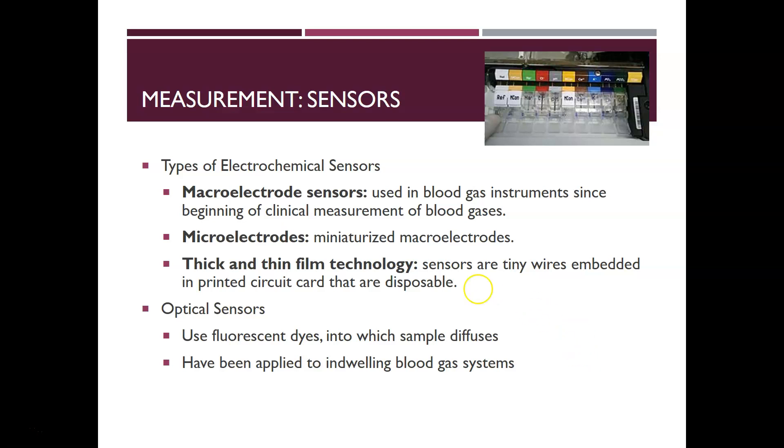Different sensor types are available. Macro electrochemical sensors have been used in blood gas instruments since the beginning of clinical measurement. As technology modernized, instruments were miniaturized to micro electrodes. There is also thick and thin film technology — sensors are tiny wires embedded in printed circuits that are disposable, used in some bedside ABG analyzers. Optical sensors also exist, using fluorescent dyes to which the sample diffuses, and have been applied to indwelling blood gas systems.